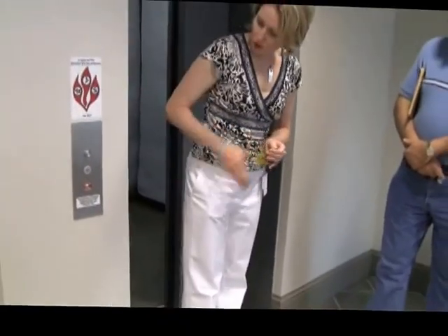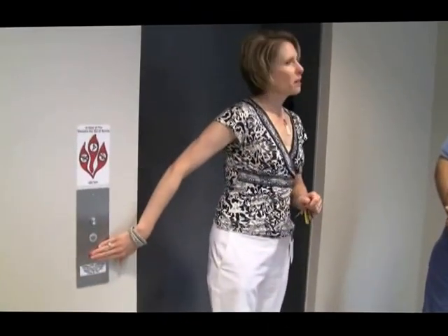So you have your fire service key switch. This should always remain in the off position. The only time it should go on is if you're doing a test or if there's an actual fire in a different part of the building and it hasn't reached your smoke heads yet. The smoke heads for the elevator are separate from the rest of your building.